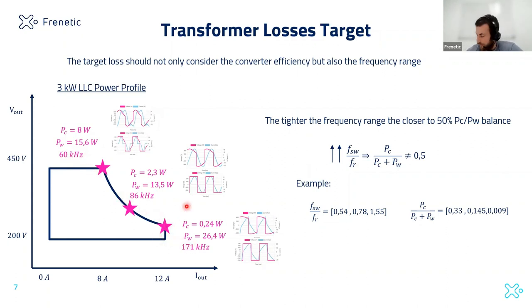Now, why I want to point this out is because, okay, we have a loss target in the transformer, but now we need to define how much of those losses should be in the core and how much of those losses should be in the windings. If you look at the magnetic design books, they will always say that the optimum is to have a 50% balance between the core losses and the winding losses, and this is true.